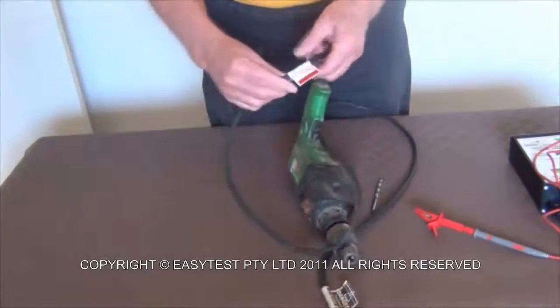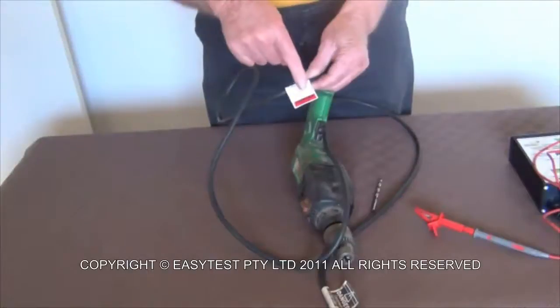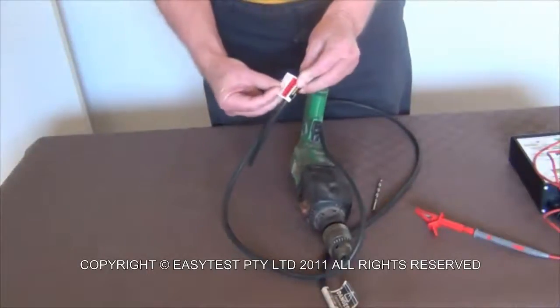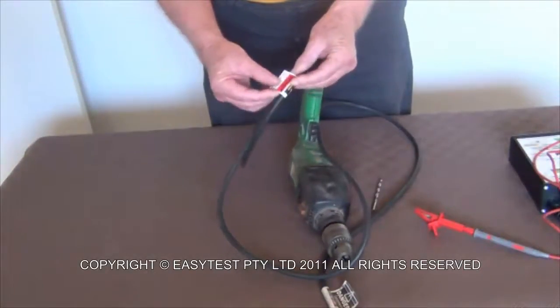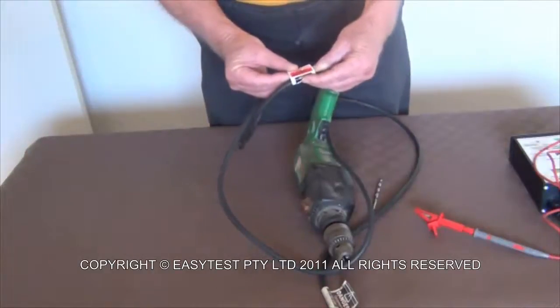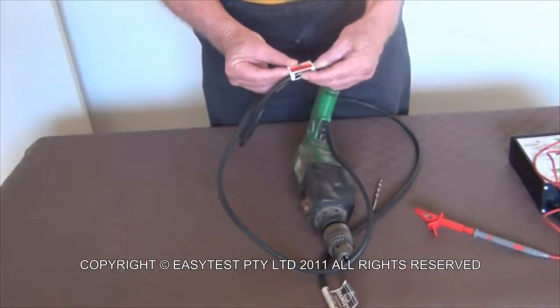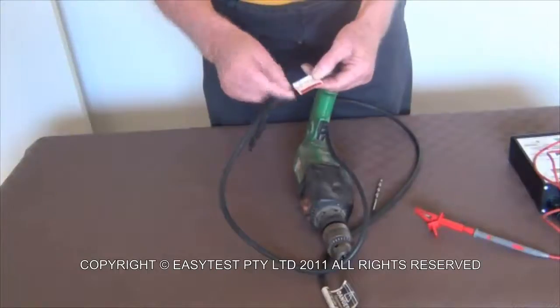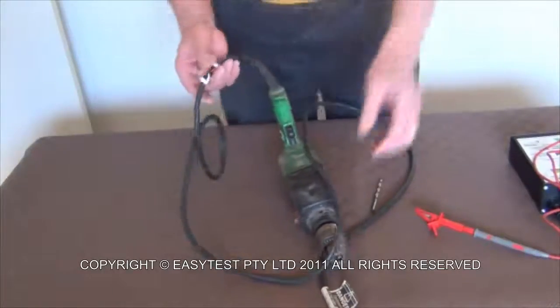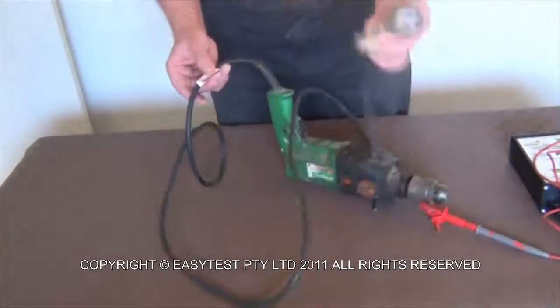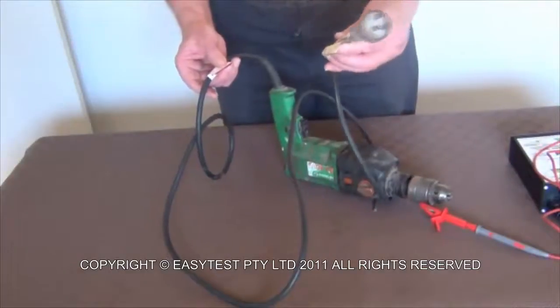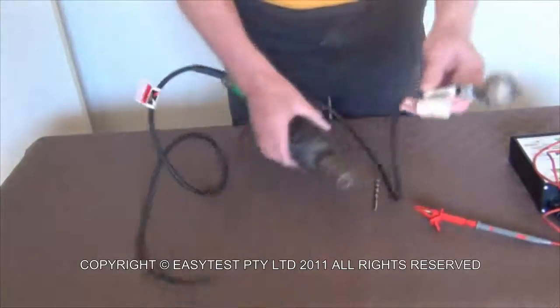These are the tags that I prefer. They're red and they have danger written on both sides, and it says this item has failed a safety test, do not use, on both sides. This one is very easy to mistake for a pass tag, and it actually was.